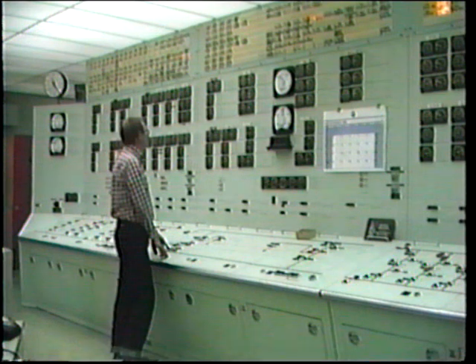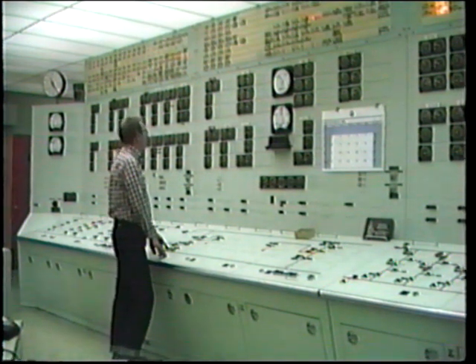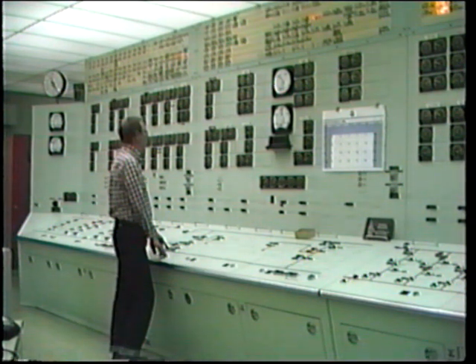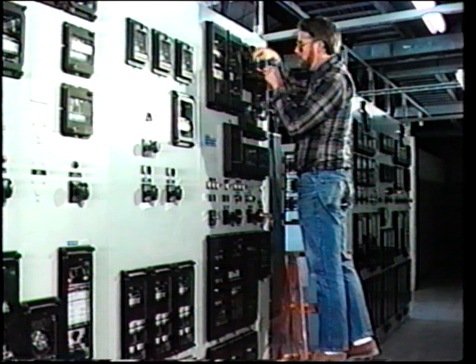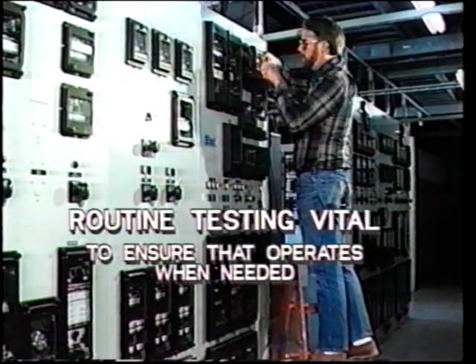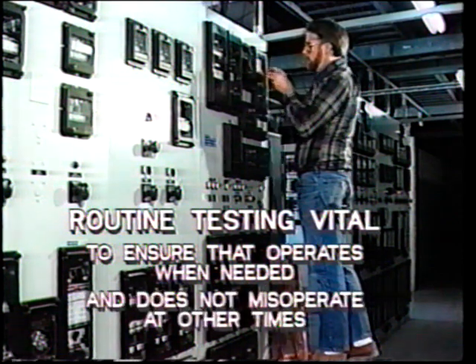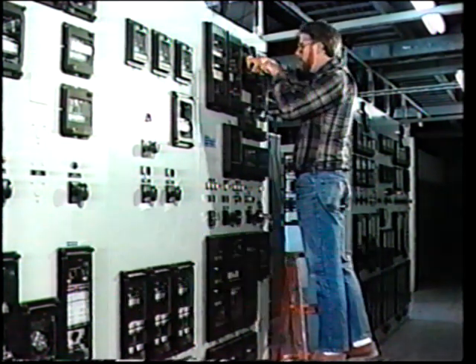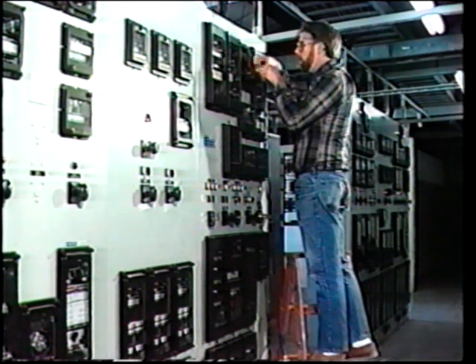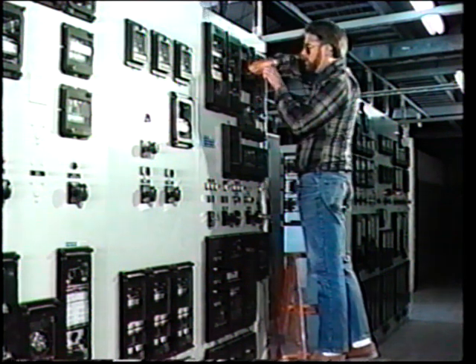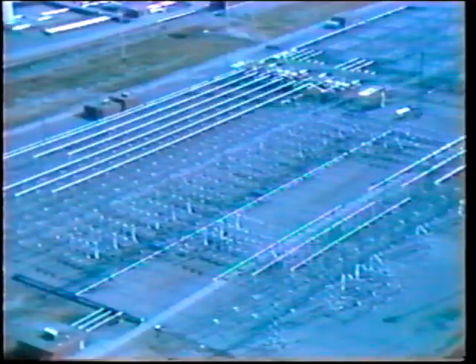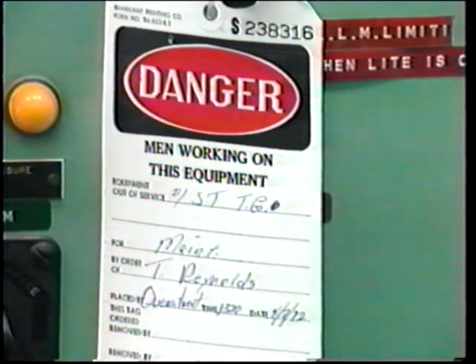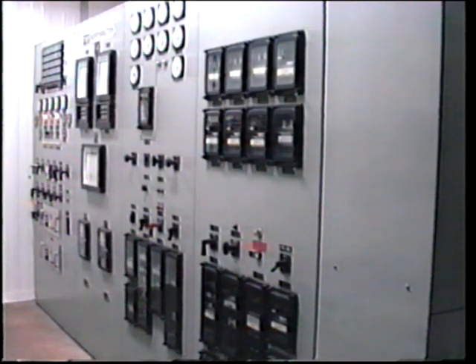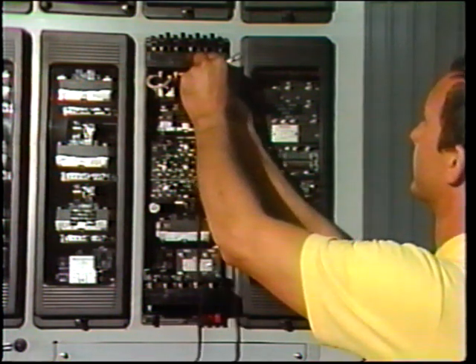Now, we know that the system operator or station operator does not like to see the relay technician turn up with his test equipment to disturb the status quo. But he knows as well as you and I that routine testing of protection equipment is vital to ensure that it really does operate when needed and that it does not misoperate at other times. However, the tester must be on his toes and take all precautions to ensure that he does not cause inadvertent tripping himself while conducting the tests. Before he even enters the station, he must be aware of the high voltage configuration. Is any equipment out of service? He must scope out the job beforehand and determine the possible impact of an inadvertent trip. You really have to know what you're doing and practice extra caution continuously.